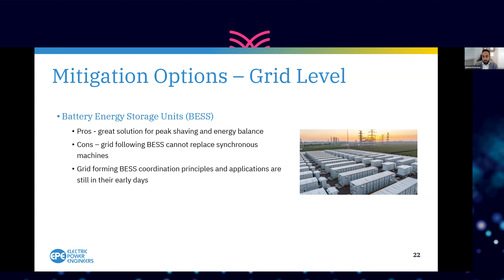We had observed at one of our client territories oscillations on their 500 kV system, ranging from 490 to 580 kV, so really a broad range of oscillations. Sometimes we were surprised that the system stayed together with that magnitude of change. What had happened was facilities were integrated piecemeal, as we noted before, without proper coordination.